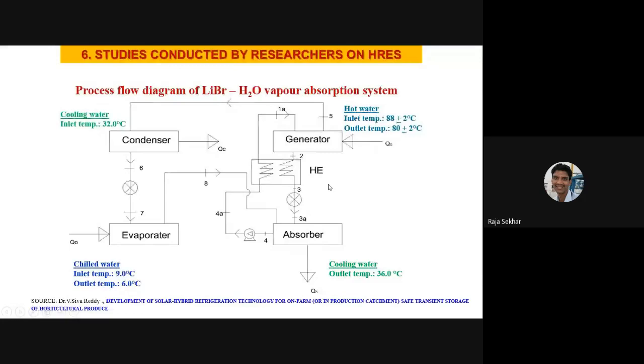I think most of you are familiar with the vapor compression system. This vapor absorption system is also similar. Instead of a compressor, you have a generator, where LiBr will be the working fluid. Once you give heat to the generator, the lower boiling point fluid will evaporate first and go on, and the remaining dilute fluid will come to the absorber. Once the vapor reaches the condenser, it will condense. Then you have a throttle valve, and finally the evaporator, where the heat is taken up. The condensed liquid evaporates, and the vapor again comes to the absorber. Both mix, and the concentrated mixture is pumped again into the generator. This is the principle of working.